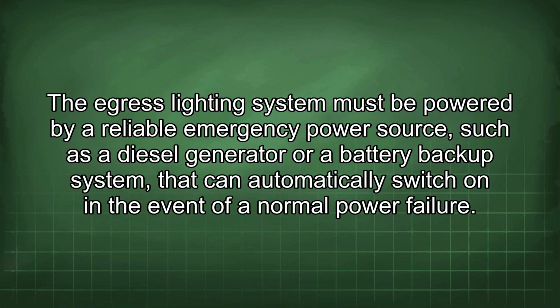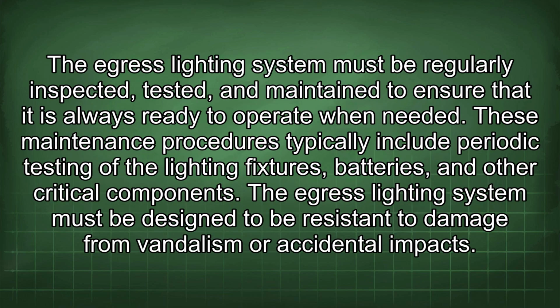The egress lighting system must be powered by a reliable emergency power source such as a diesel generator or a battery backup system that can automatically switch on in the event of a normal power failure. The egress lighting system must be regularly inspected, tested, and maintained to ensure that it is always ready to operate when needed. These maintenance procedures typically include periodic testing of the lighting fixtures, batteries, and other critical components.